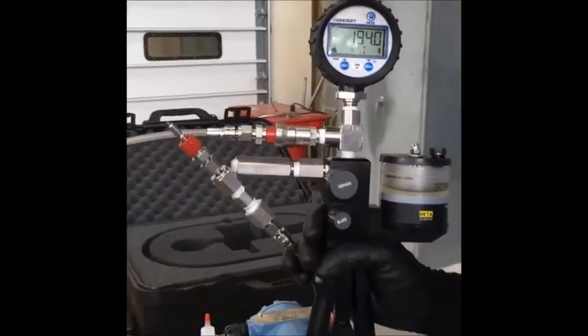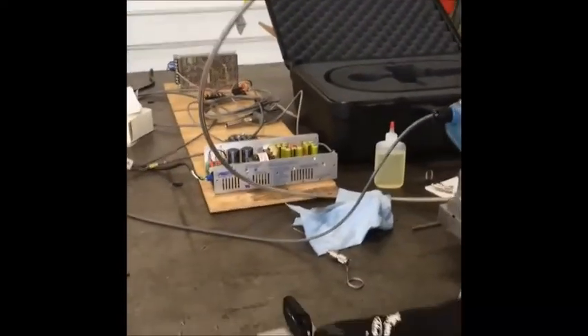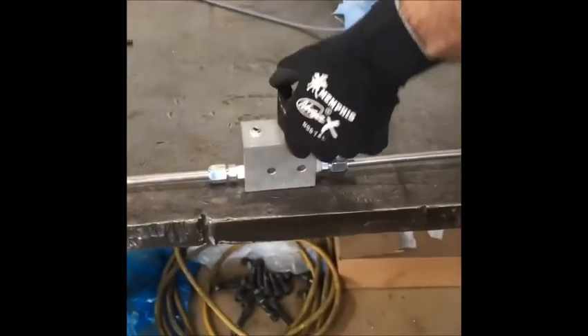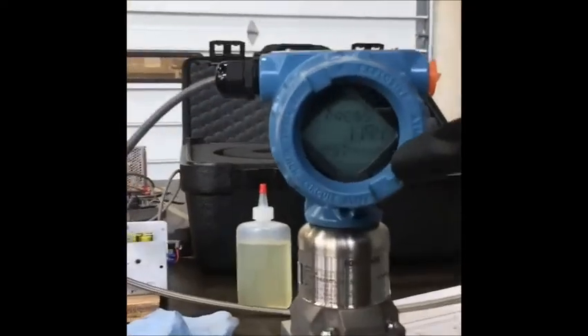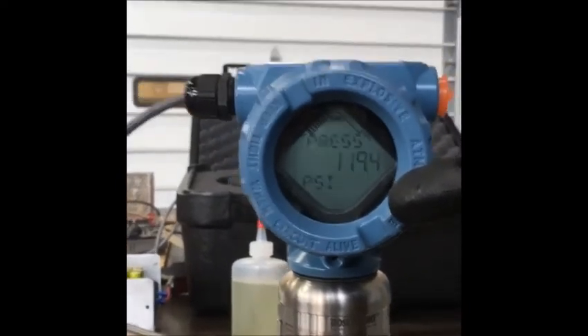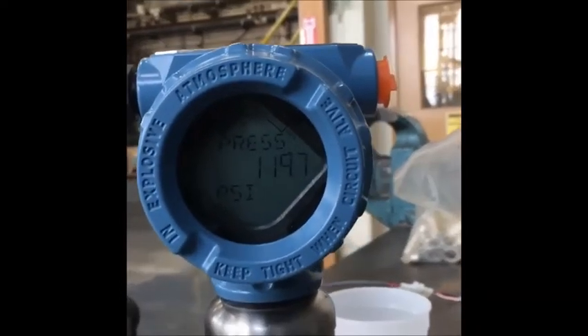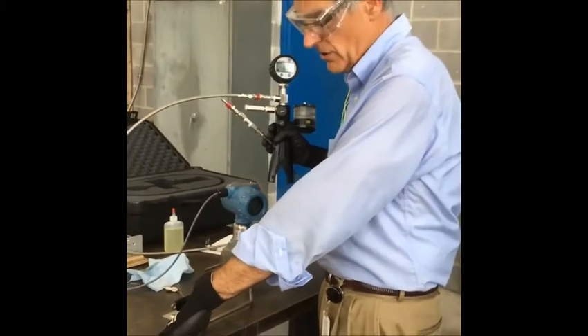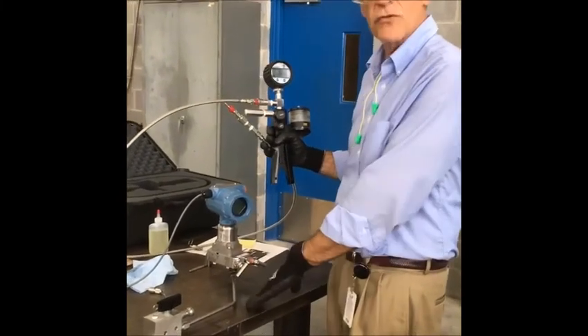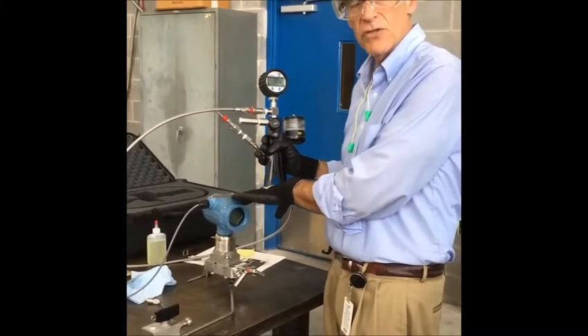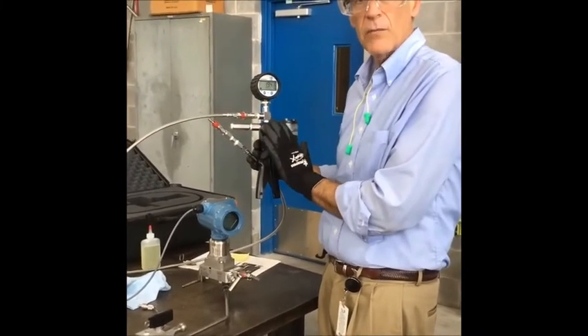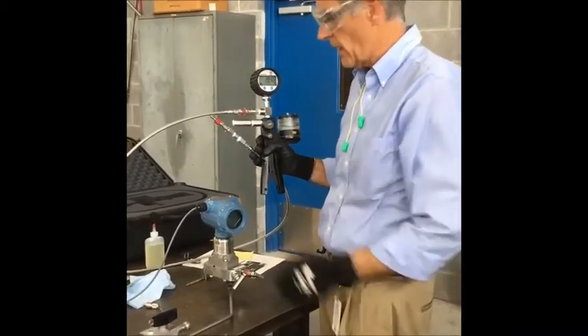Okay? As far as my system is concerned on the test block, I'm going to switch that back to run position so that the pressure now on my high pressure cutout will read real system pressure. It's not reading just the false oil pressure that I pumped into it. One advantage of this test method is this block has a check valve in it so that if a real high pressure occurrence happens while you're doing the calibration, the check valve opens, the high pressure still goes through the high pressure cutout. It will still cut the machine off, even if I'm only part of the way through the calibration. So that's partly what makes this such a safe method.